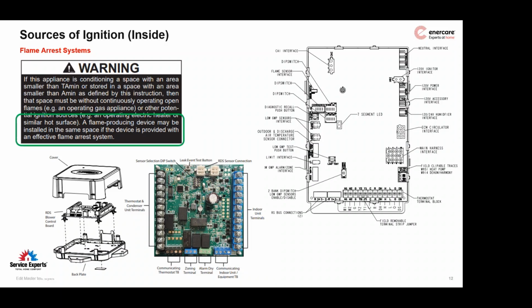As far as I know, Carrier is not planning on upgrading their systems to include an A2L or low GWP equipped PCB into their furnaces. They're just going to stick with their standard furnace model lineup, and that external board will be put on. Goodman, however, is going to go the same way Lennox did. They're going to have an external board for those AC or heat pump only systems that are being installed with a legacy system, but they're also upgrading their internal PCBs to be equipped with a low GWP PCB. That's a lot of letters together. They're going to use the same strategy as Lennox.